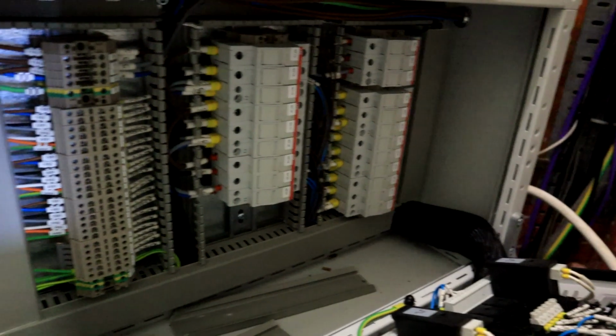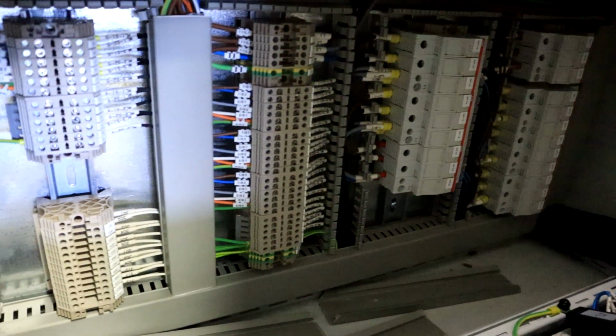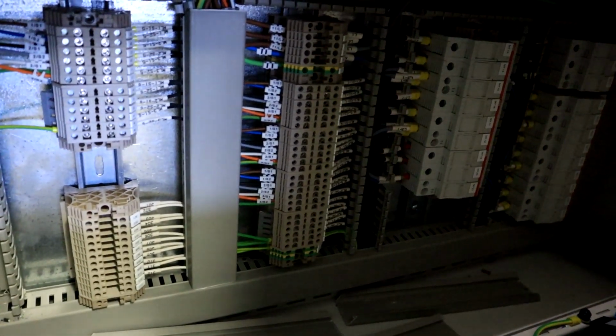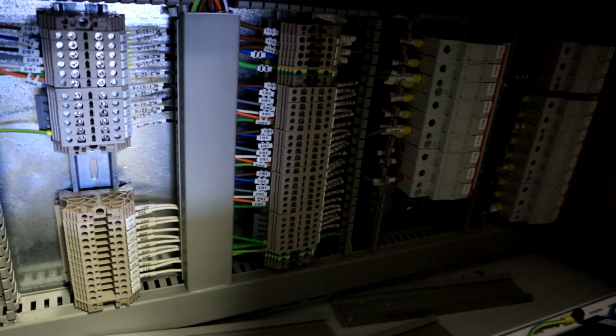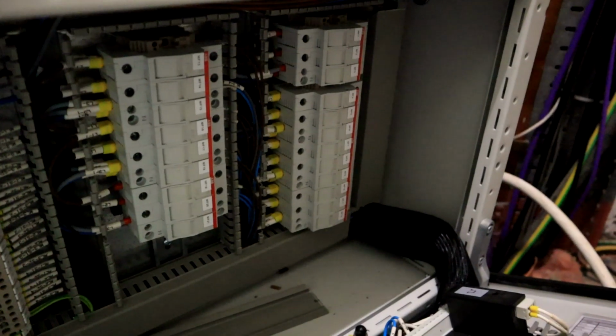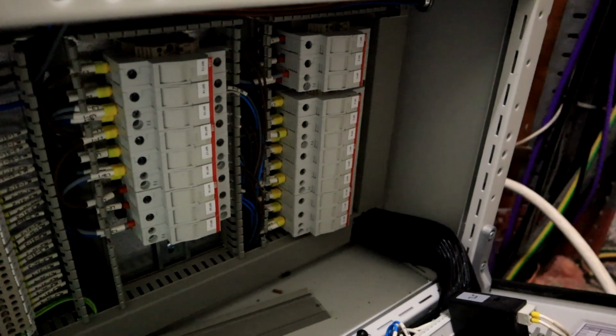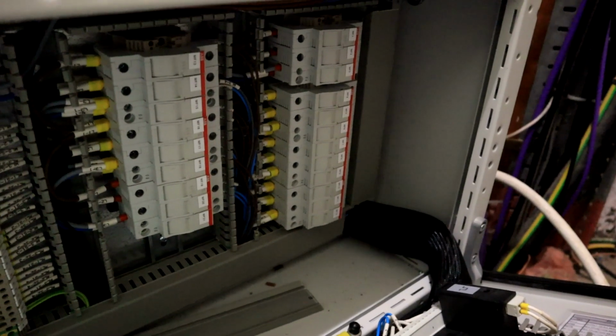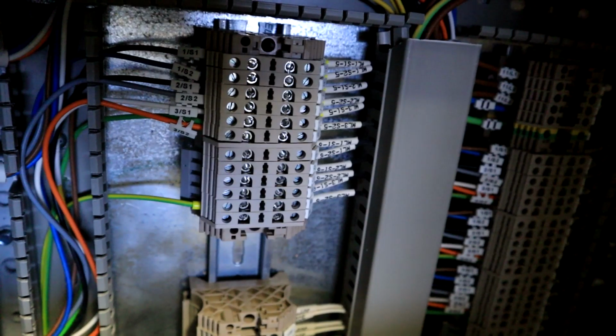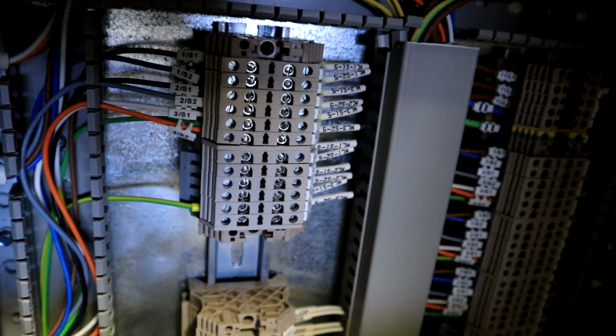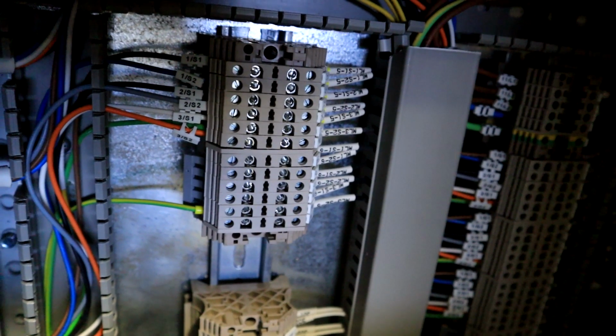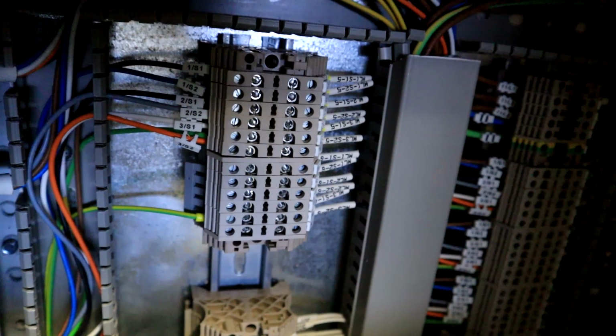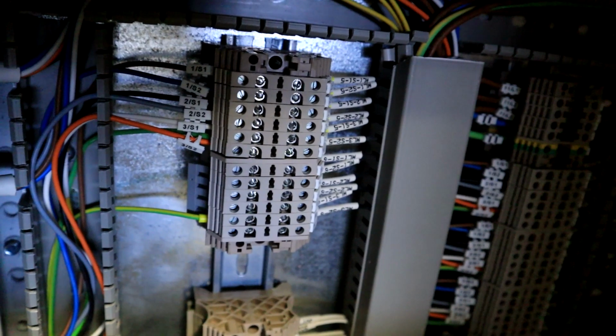Within the metering panel there is a group of fuses for the voltage reference for each meter and a group of terminals for the current transformers. The fuses mean that the voltage to each meter can be isolated without switching off any supplies to the building, and the CT terminals mean that the current transformers can be short-circuited, allowing the safe removal and replacement of each meter, again without disruption to the building users.